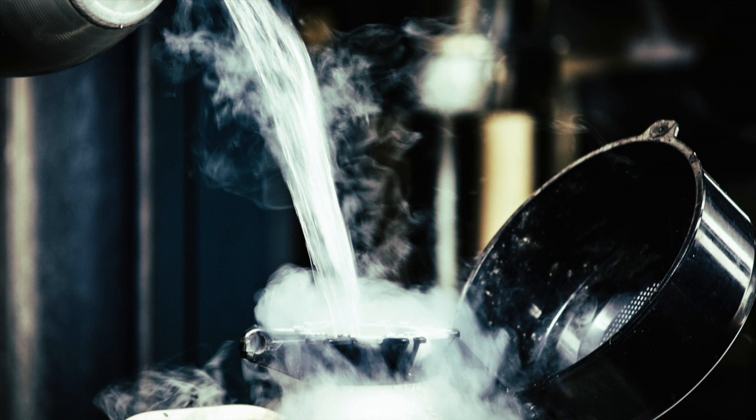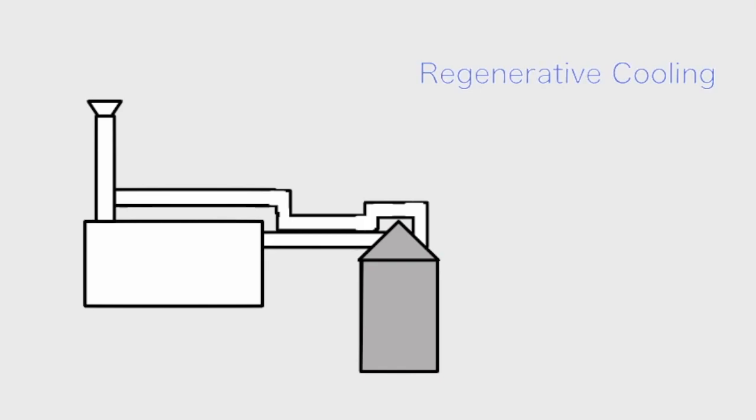When liquefying gases such as oxygen or nitrogen, an extension of the Joule-Thomson cooling effect is used. This is known as regenerative cooling. The gas first enters the system where it is compressed and its temperature is increased.